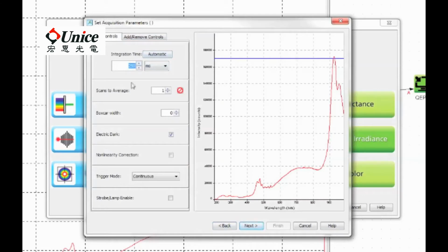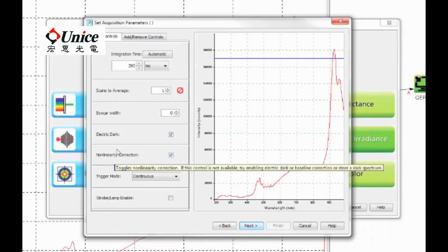First, choose the integration time. A longer integration time is best as it improves the signal-to-noise ratio, but the calibration source may have high intensity, so simply choose the integration time that brings the highest point in the spectrum up to the blue line displayed, and take care not to saturate the spectrometer. For best results, turn on the electric dark and non-linearity correction, and opt for a number of averages. Once you have chosen these, click Next.